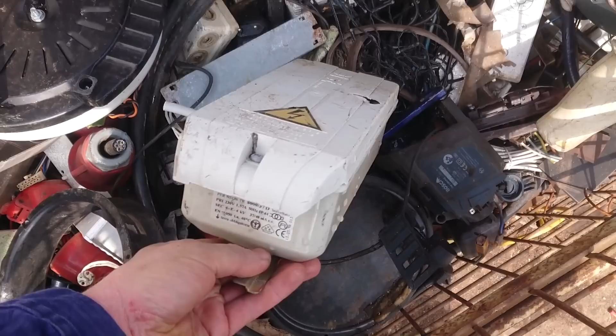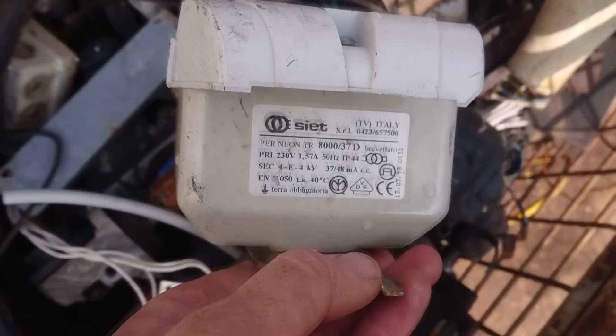So now that we're done with that, we can still have a brief look at this neon sign transformer here. Since I don't have the equipment here to easily build a neon tube to test the transformer that way, we can just hook it up to the isolation transformer, slowly stepping up the supply voltage and see if we can create an arc. And I want to say in all clarity that this is not a particularly safe setup, and I absolutely do not recommend that you play around with these high voltage transformers yourself.